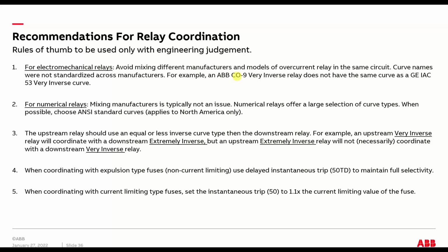So the take home is, if you're in an electromechanical world, avoid mixing different manufacturers and models, because they're not the same. It can be done, but it makes your life more difficult because they're not the same type curves. Most of you probably won't get into that situation anymore because you're not speccing new electromechanical relays. For multifunction numerical relays, doesn't matter, because most all relays have a whole selection of different curves you can pick. So they'll have ANSI standard curves and IEC standard curves. The only thing to remember is whatever you're picking, do the same thing. So if you're going to do ANSI, make sure all your curves that you use in various relays are all ANSI, and you're good to go.